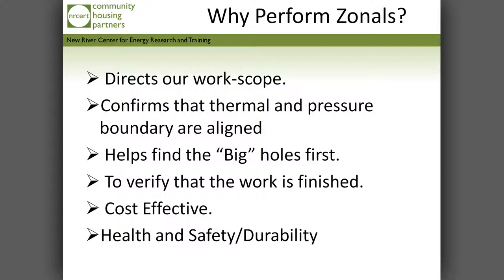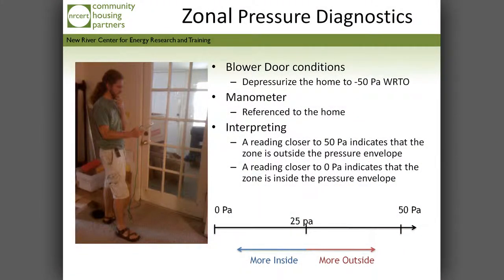Health, safety, and durability — tracking down holes that are connected to spaces we don't want to be breathing from: the crawl space, the attic, through a dirty wall. The key is that we're not worried about negatives and positives; we're worried about absolute numbers — zero to fifty. The negative or positive simply depends on where you put your hose on the manometer.